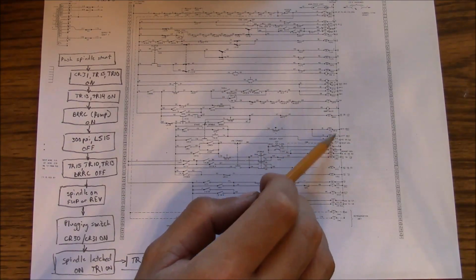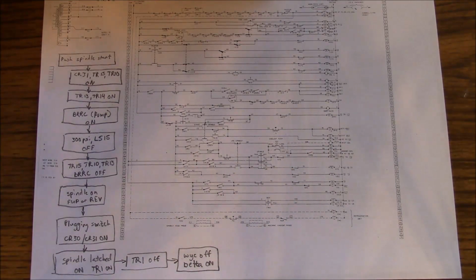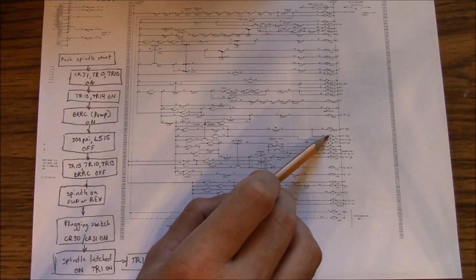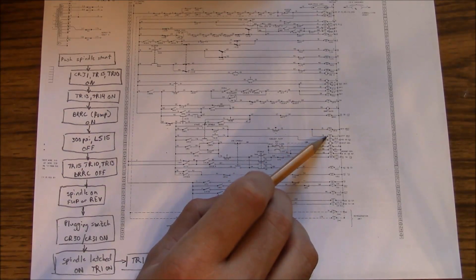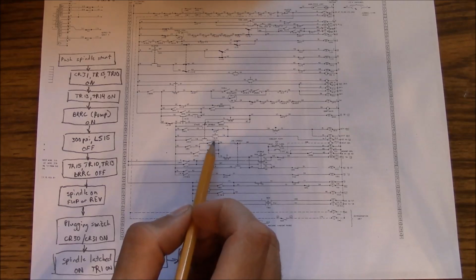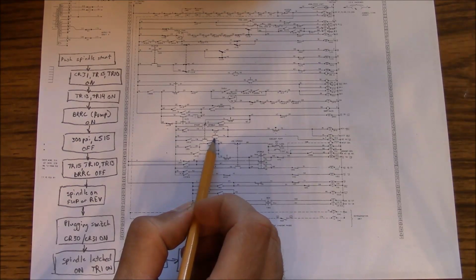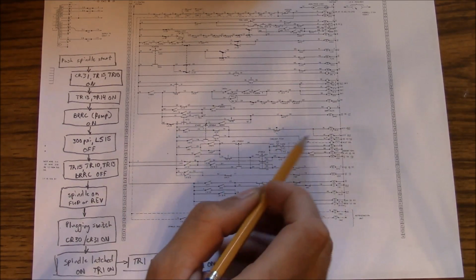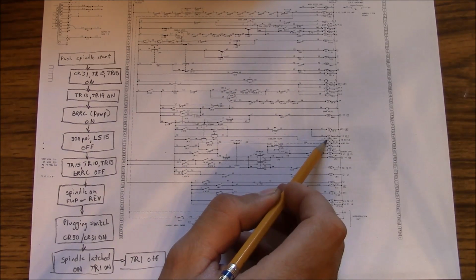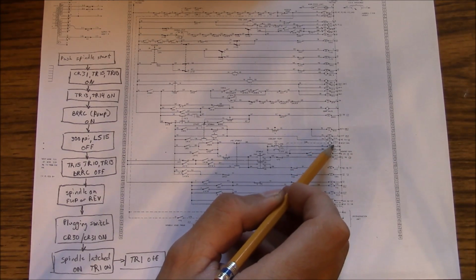Those are timer relays, and I believe those are time off delay relays. That means that once the coil is de-energized, they remain closed for maybe 1 or 2 seconds depending on how the relay is set. So once those 2 contacts or timer relays are started, this TR15 right here is going to close, and that's basically going to latch the CR31 coil on.